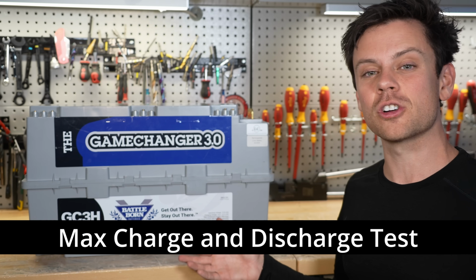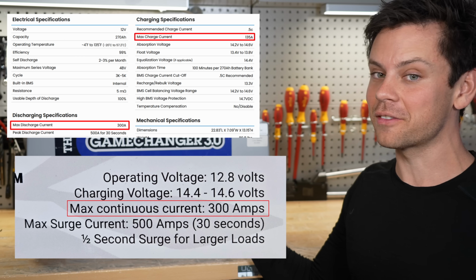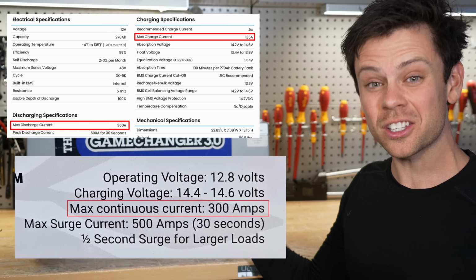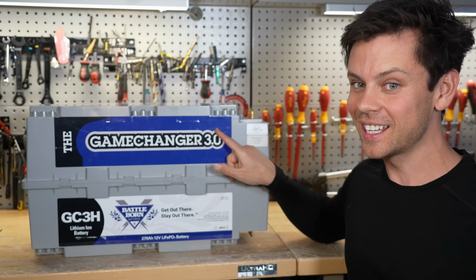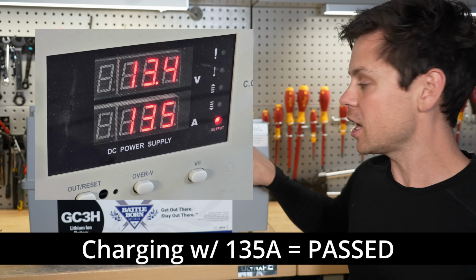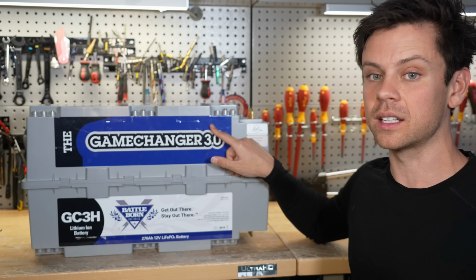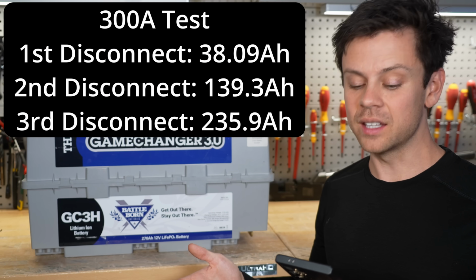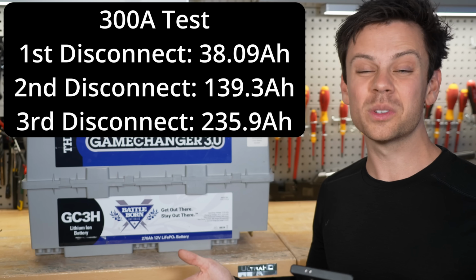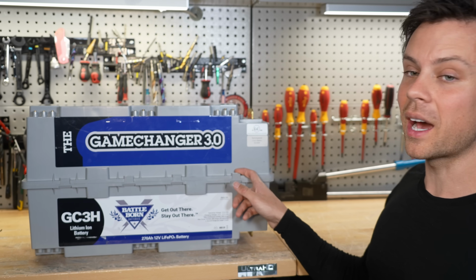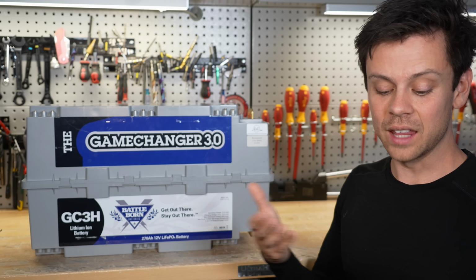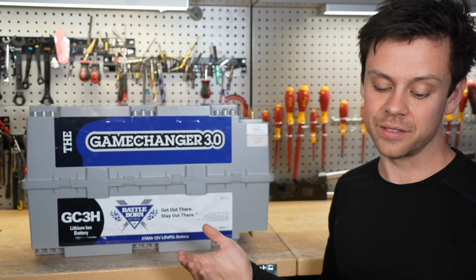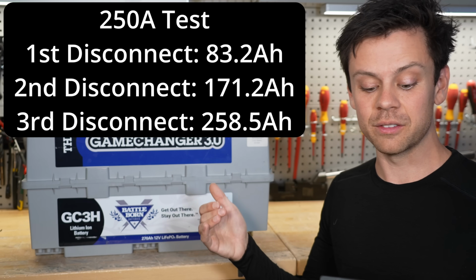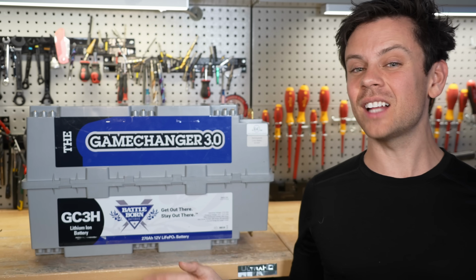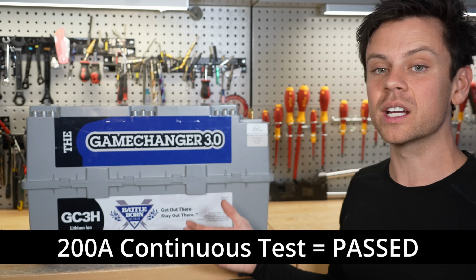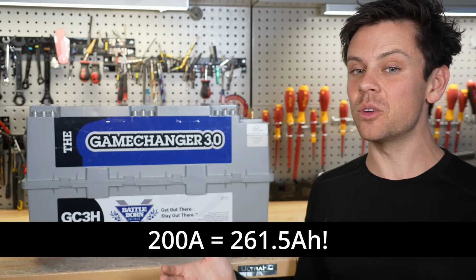Next test was max continuous charge and discharge. The data sheet says 135 amp charge and a 300 amp continuous discharge, but when I tested it, I wasn't able to do that. I could charge all day with 135 amps, but when I discharged with 300 amps, it would disconnect a lot. First disconnect was at 38 amp hours, next at 139, and the third at 235. I kept letting the battery cool down and testing again, and it would cut off every time. So I lowered it to 250 amps and got 83 amp hours, then 171, then 258. It wasn't until I lowered it to 200 amps that it could actually run a continuous load, and with that test I pulled 261.5 amp hours.